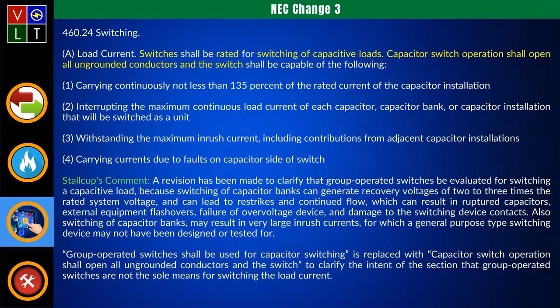It seems like that would mean you have more control over what loads you're introducing on the system, so that's probably a good change. Yeah, and they made it very clear that that capacitor switch operation is going to open all your ungrounded conductors and the switch, and then it tells you what it's capable of for the following. Basically, that's all about evaluating the switch due to capacitive load and the rupturing and everything else that can happen. Wow, okay, that's probably a great change.